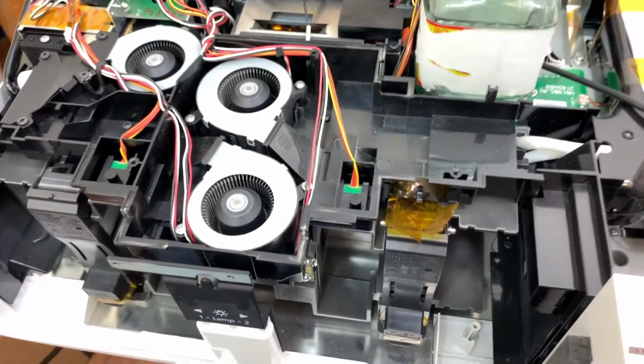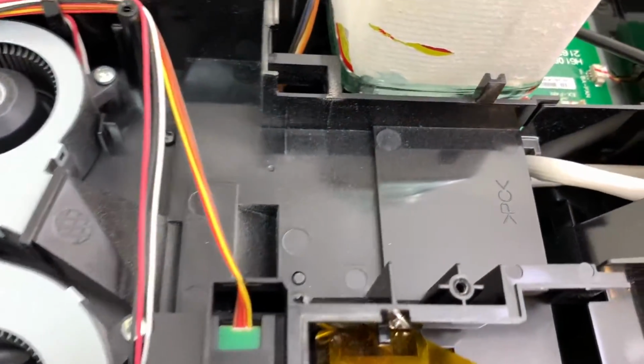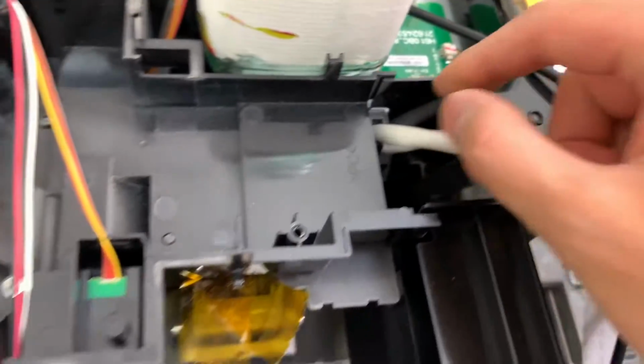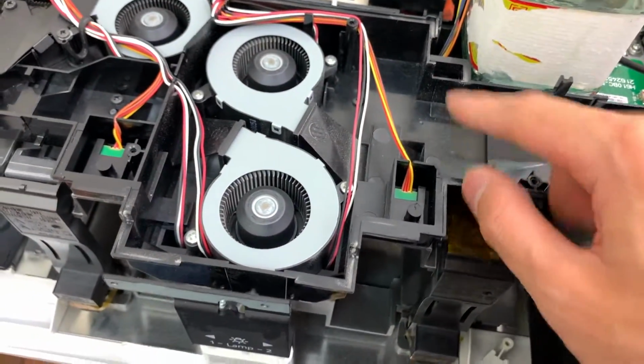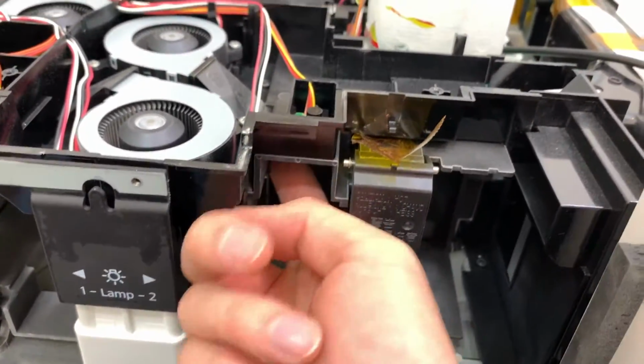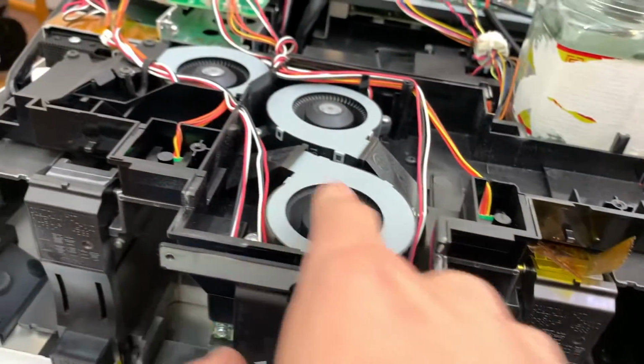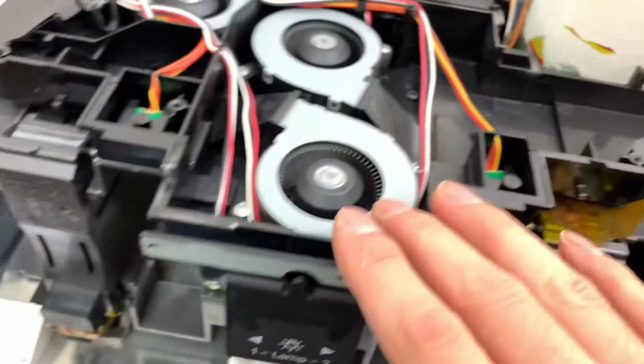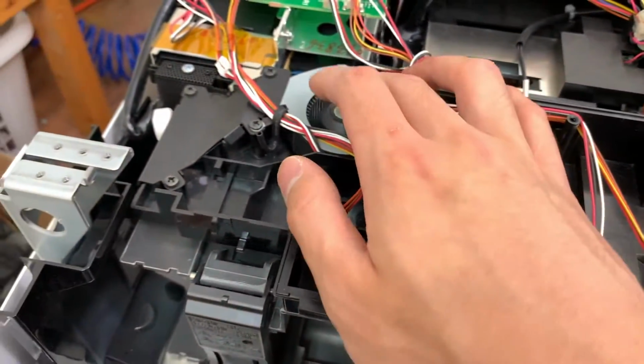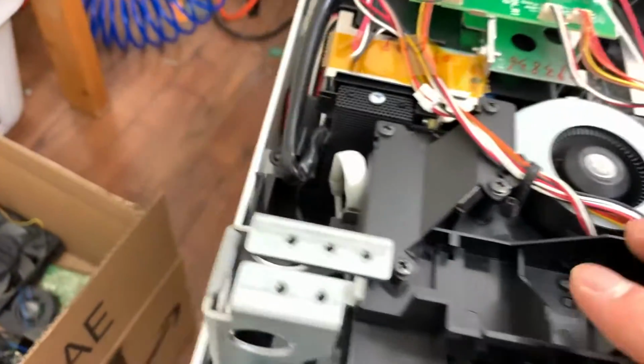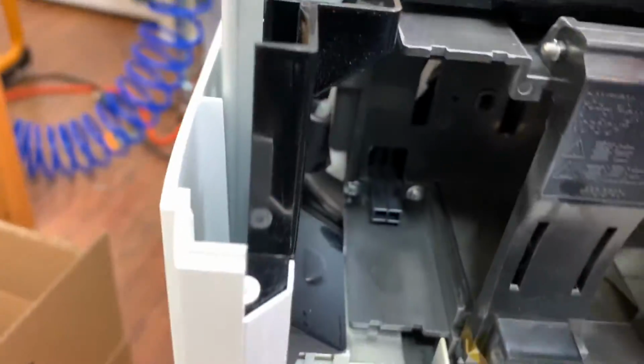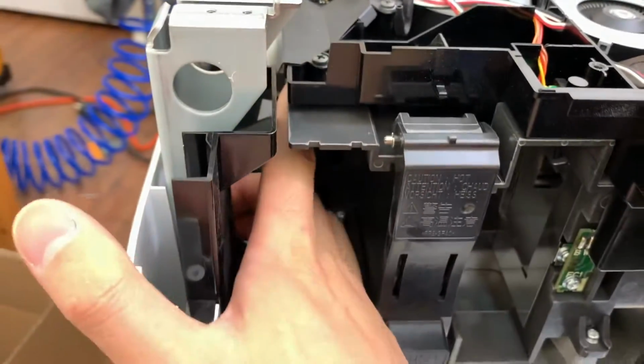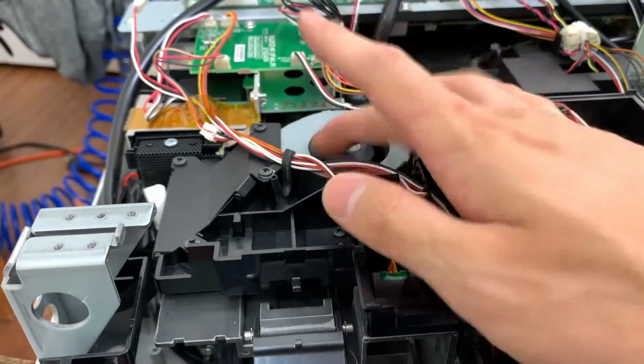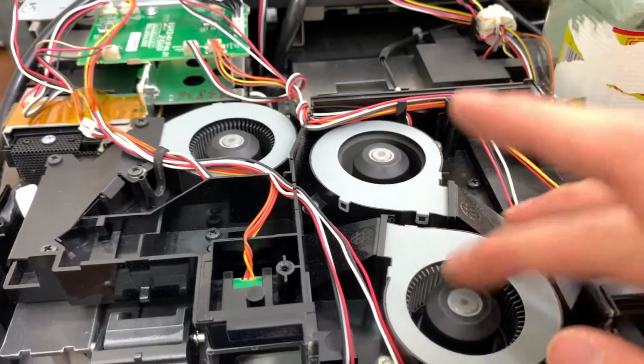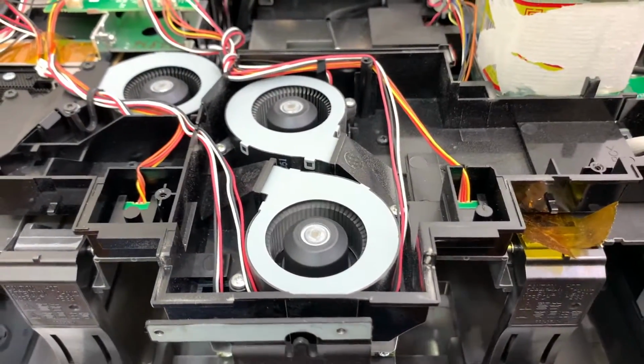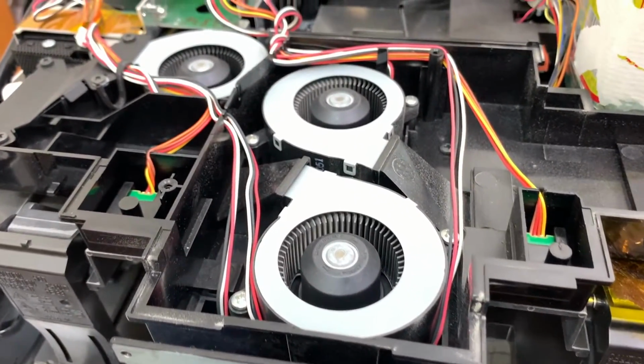Here's a cover, and under here we can see the fans that cool the lamp. The lamp seems to require quite a high pressure to blow air through the lamp housings, I'm guessing. So they've got these really small fans, only 3 of them, and the lamps are like 380 watts each. The big fans in the back are actually just exhaust fans, they don't seem to pull the air through the lamps. I don't have lamps so I don't know how they're arranged, but just 3 small blowers, probably like 60 millimeters, good quality though.